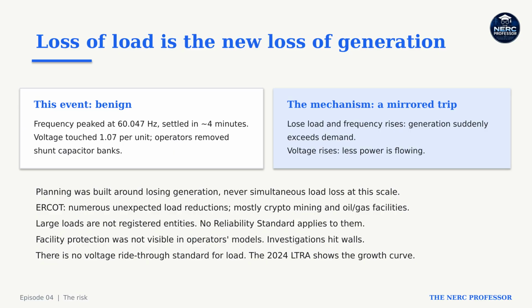and this was not a one-off. ERCOT has seen numerous unexpected load reductions during disturbances, mostly power electronic load at crypto mining and oil and gas facilities. When operators tried to investigate, they hit a wall. These loads are not registered entities. No reliability standard applies to them. Some of their protection wasn't visible in anyone's models, and there is no voltage ride-through standard for load. None. The 2024 Long-Term Reliability Assessment documents how fast this class of load is growing. Some of these facilities want to connect in months, not years, so NERC moved.